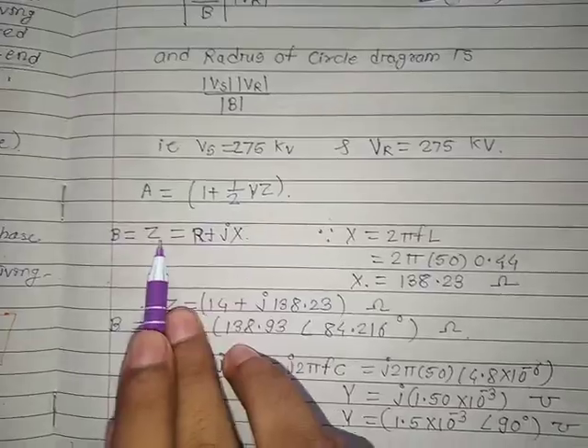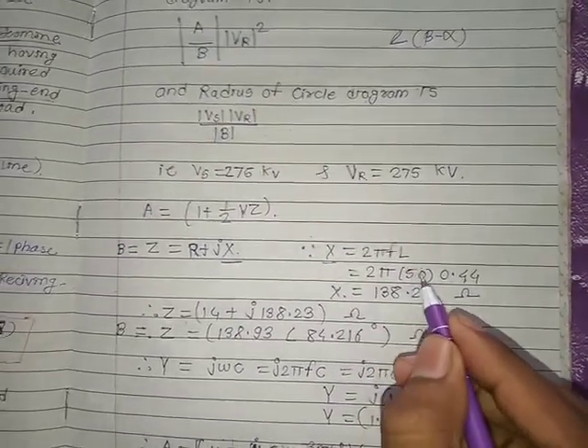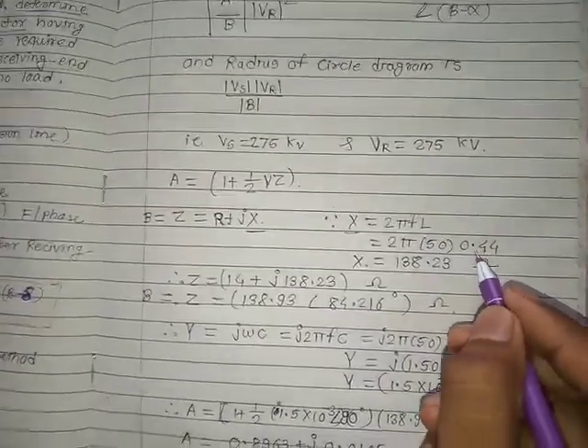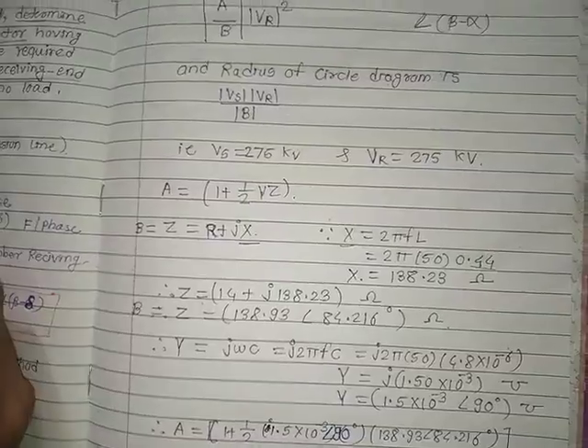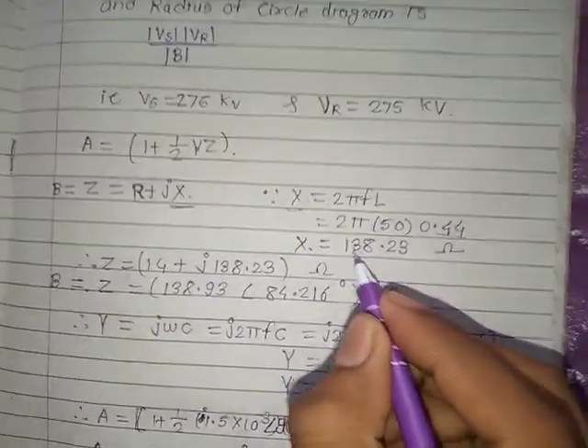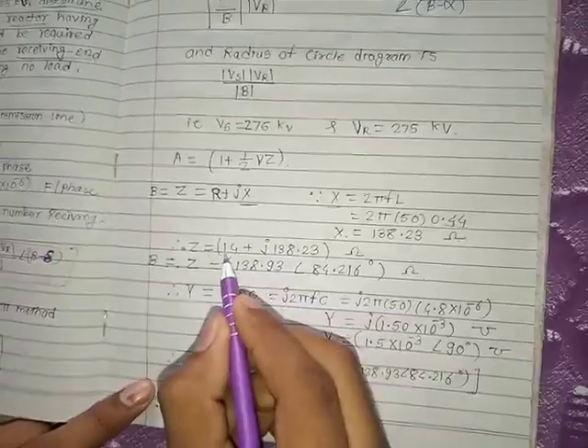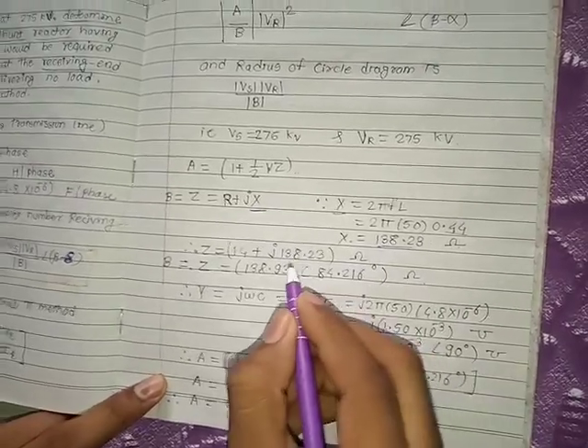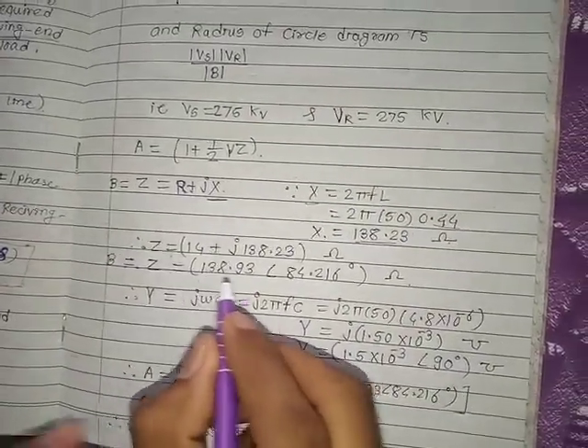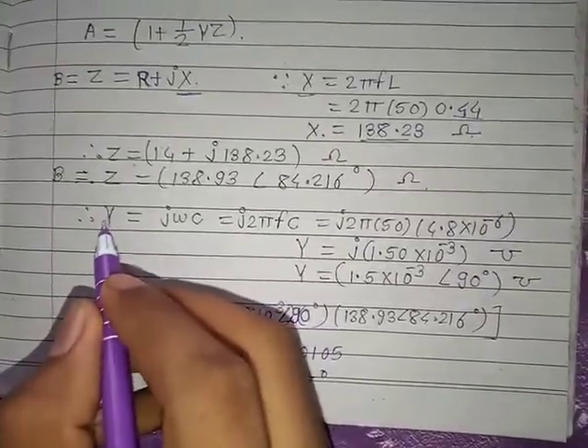A = 1 + YZ/2 and B = Z = R + jX. We need to calculate X: X = 2πfL = 2π × 50 × 0.44 = 138.23 ohm. So Z = 14 + j138.23, which in polar form is 138.93 ∠84.216° ohm.